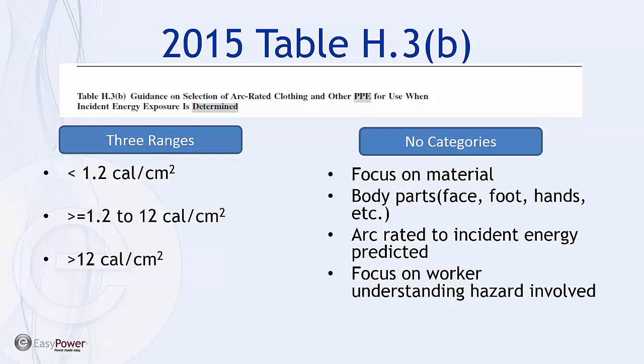We'll notice also that we can, as I probably have said it 3 times now, we can suit up to the arc-rated incident energy. Frankly, I read this as a focus on the workers understanding the hazard involved. And while it may have been easy to say, okay, well, I was just this category 3 or category 2 and I walk off and mindlessly put something on, there really is, I think, an encouragement, a push to better training of people involved, that there really is a danger, a significant danger, and we need to be involved. We as workers, with qualified workers, need to understand that we have a responsibility, and not only correctly choosing the PPE, but making sure that we're using it and we're aware of these 5 assumptions that are being made.